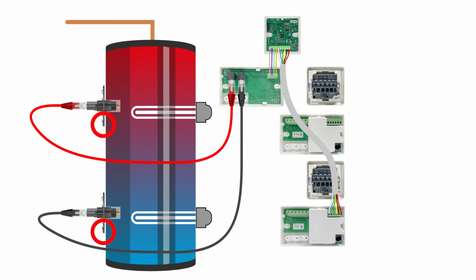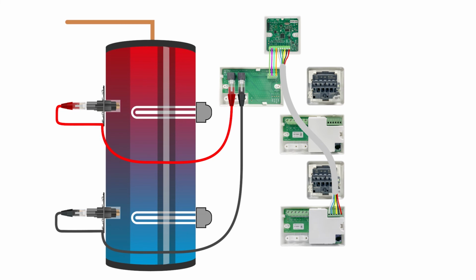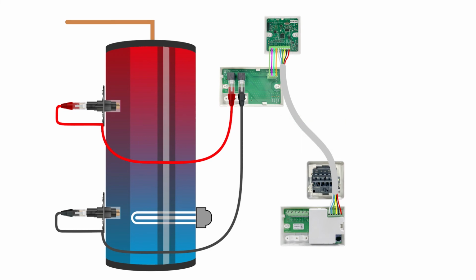At the probe end, use the 4 loops on the flange to secure the probe cable tidily with 2 cable ties. For a single element tank, the procedure is the same as described, but with the omission of the slave relay.